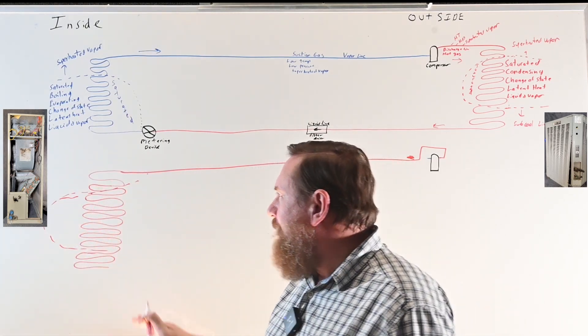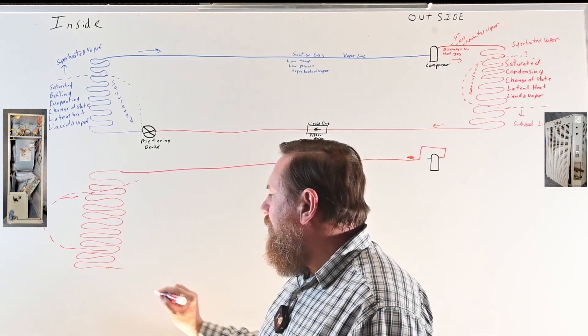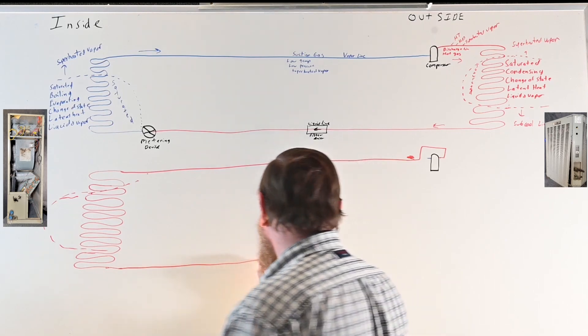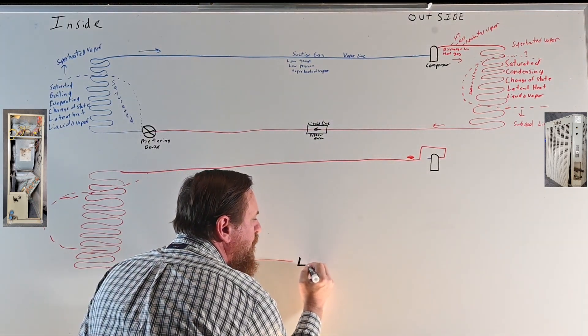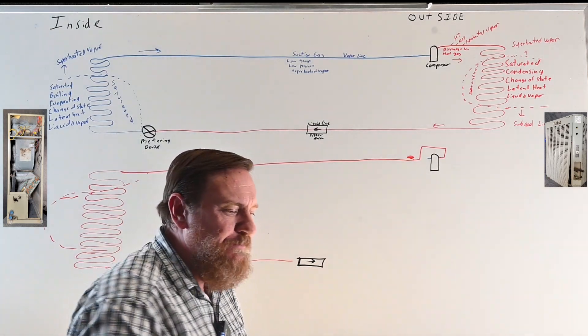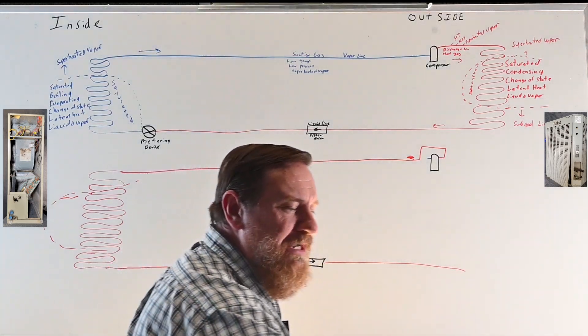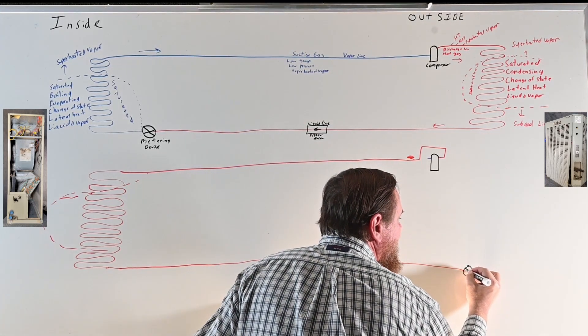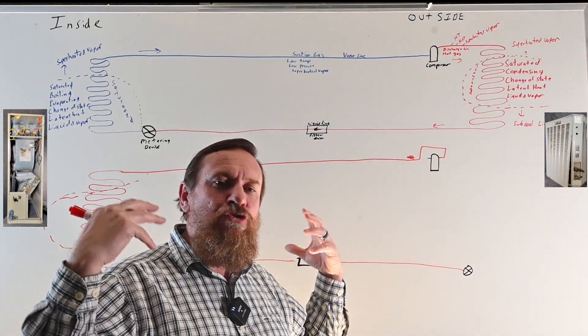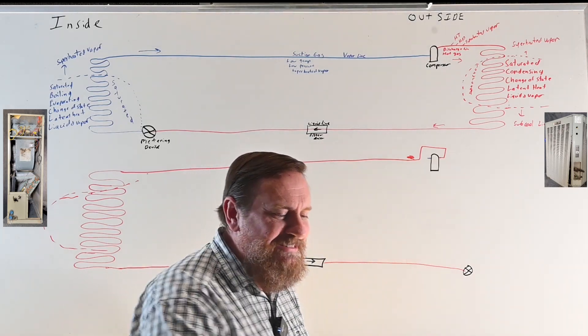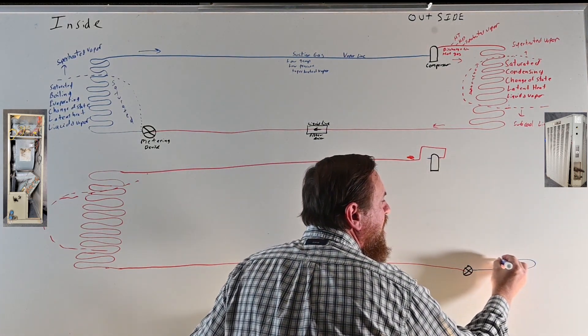This is all happening inside. We're going to have to bypass our original metering device, take it out of circuit, and move that metering device. We keep this as the liquid line, but we have to turn our liquid line filter dryer around — put a new bi-directional filter dryer facing the opposite direction. We go through our liquid line filter dryer and continue to our outdoor coil, where we now need that metering device. We add the metering device there; we must have that pressure drop.